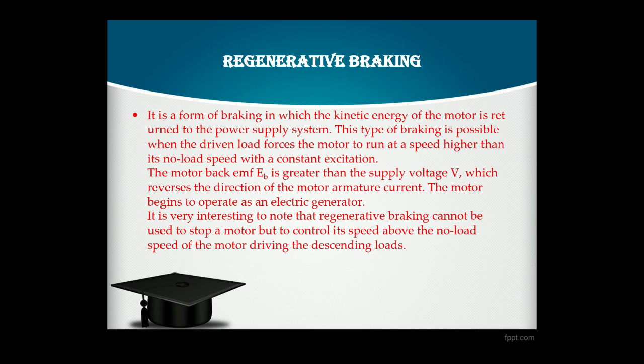It is very interesting to note that regenerative braking cannot be used to stop a motor — there is no stop phenomenon in regenerative braking. It is used to control the speed above the no-load speed of the motor driving descending loads. When a motor is running above its no-load speed, regeneration of electrical energy occurs.